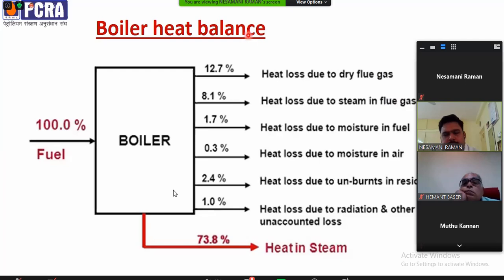This is a boiler heat balance diagram. If we give 100% fuel as input energy to the boiler, the efficiency will be 73%. That heat will be in the steam. What are the losses? If you see, the highest loss is almost 12%.